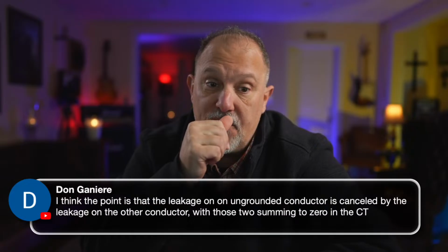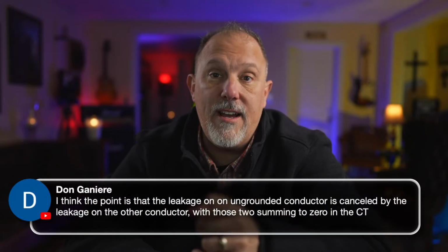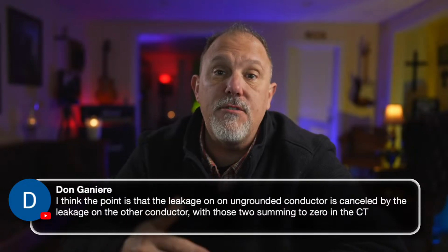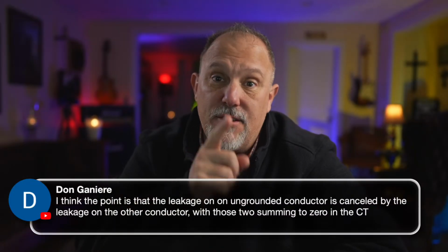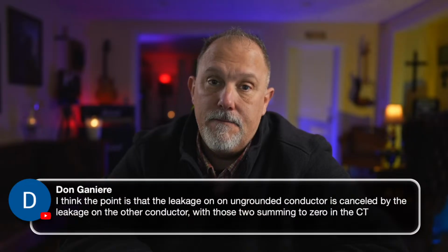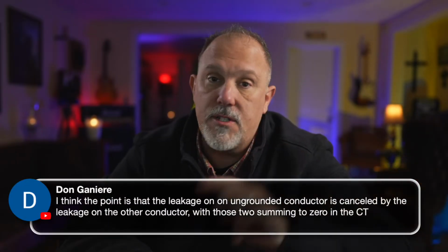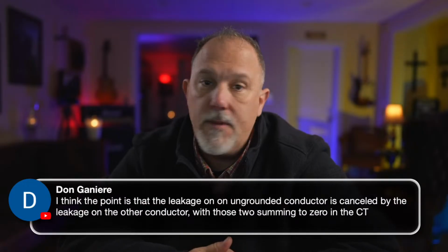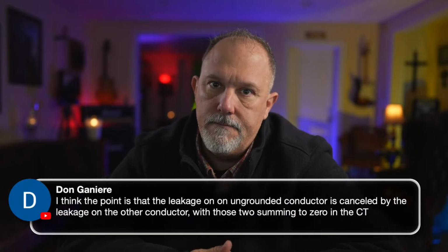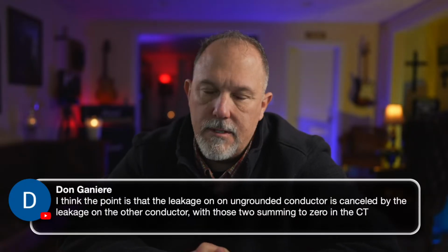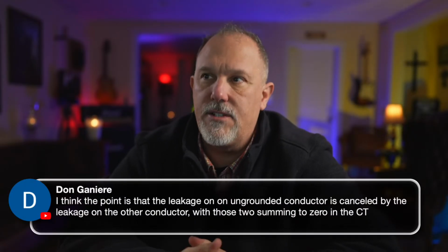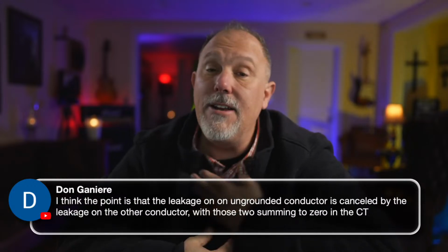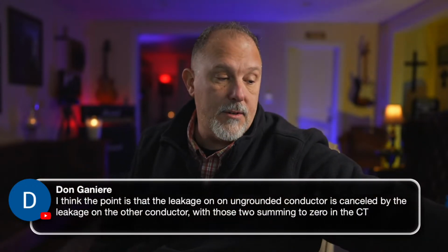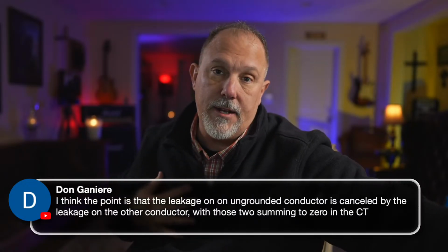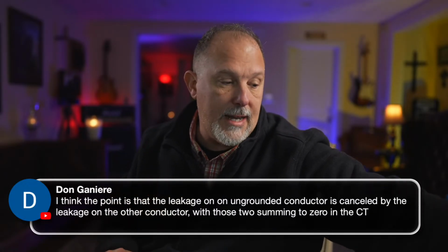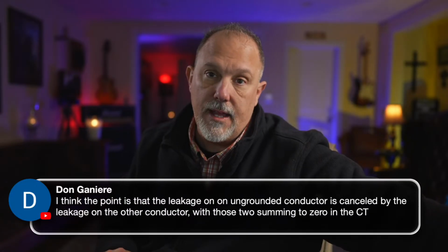In fact, Don, if you watch that other Q&A Friday, we have a real world scenario of over 1,000 feet of conductor that the manufacturer said will not work on a GFCI, and it works perfectly fine. The leakage currents aren't going to cancel. I just don't agree with it, Don. That's based on my experience and my knowledge of these applications. I don't believe that would be the case.